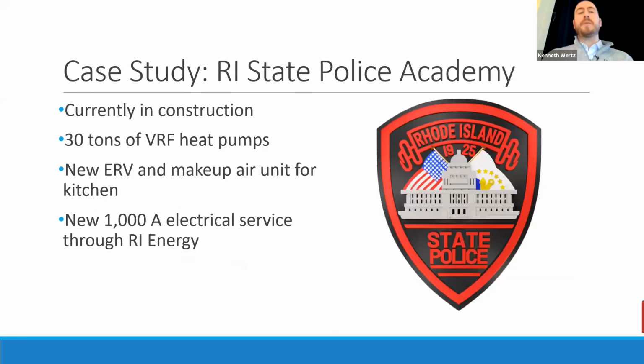All right. And then the last one I'll just mention real quick, a smaller building. They went with VRF as opposed to the more expensive hydronic systems. So this is the training academy for the Rhode Island State Police. It's only a 10,000 square foot building. They needed 30 tons worth of VRF heat pumps. But just for context here, they went with a new 1,000 amp service, whereas they had 400 before. So 2.5 times as much electrical demand, electrical capacity for the building to be able to support it.